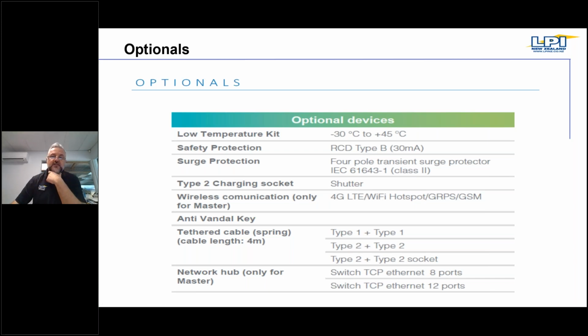We can have surge protection optional inside the EV chargers or also at the point of supply. Our surge diverters and surge filters come with the capability to monitor their states through Bluetooth communication on your phone. Basically, you download a free LPI app, and you can see exactly how many surges you've had, what the temperature is inside the surge unit, what the power quality is, and the maximum and minimum voltage that your EV charger has ever experienced.